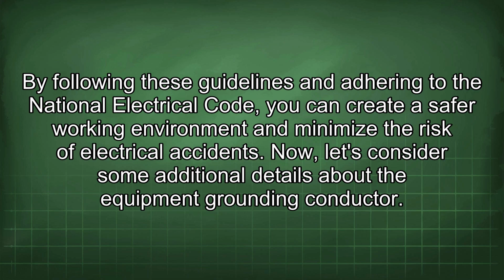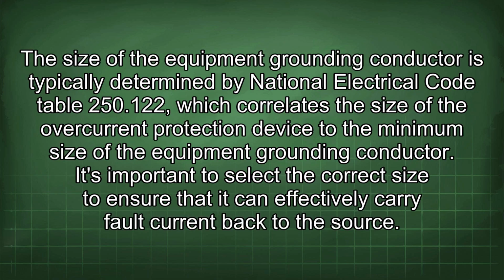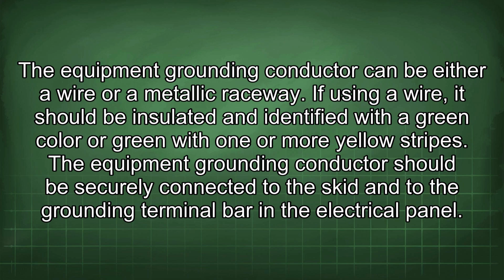Now let's consider some additional details about the equipment grounding conductor. The size of the equipment grounding conductor is typically determined by National Electrical Code Table 250.122, which correlates the size of the overcurrent protection device to the minimum size of the equipment grounding conductor. It's important to select the correct size to ensure that it can effectively carry fault current back to the source. The equipment grounding conductor can be either a wire or a metallic raceway.